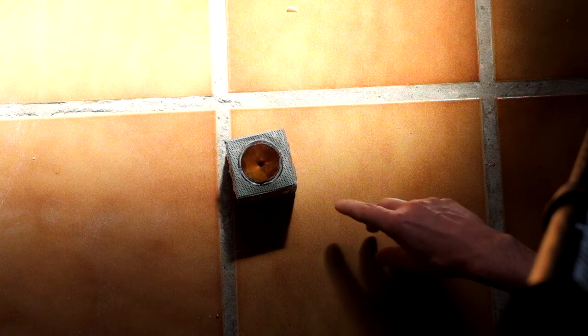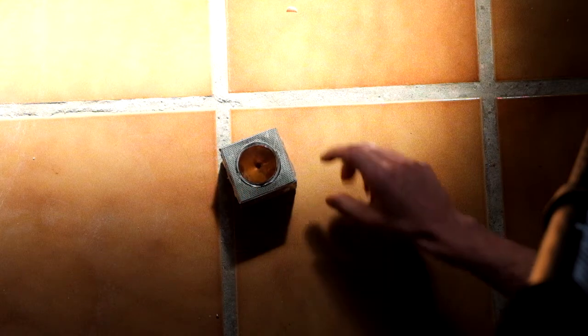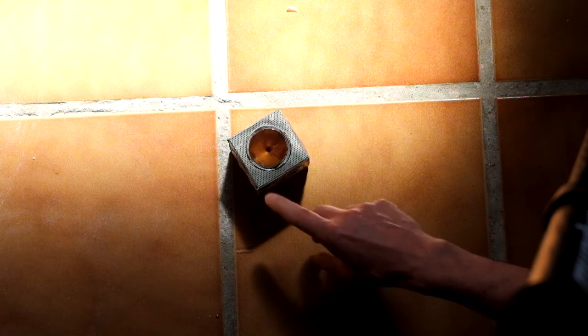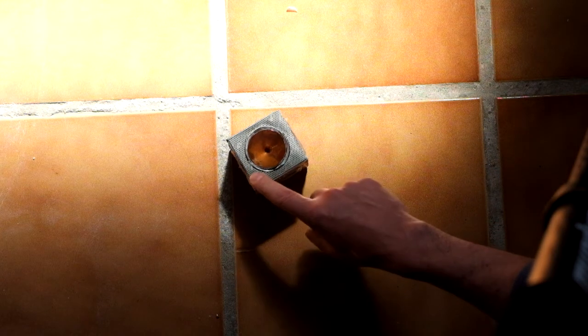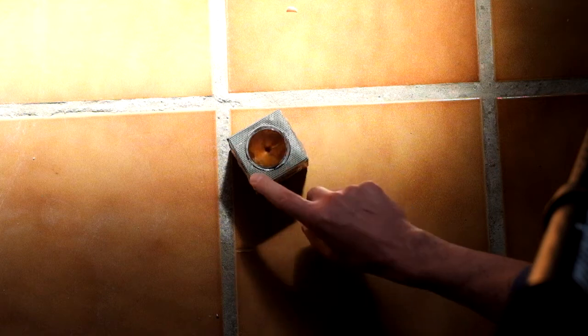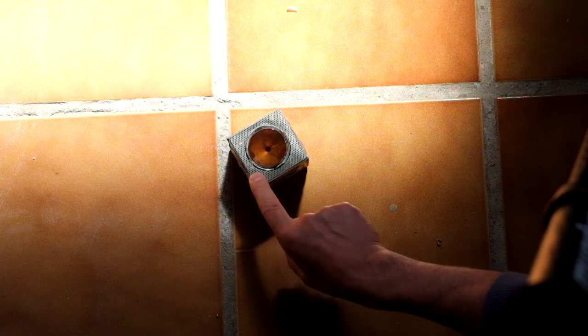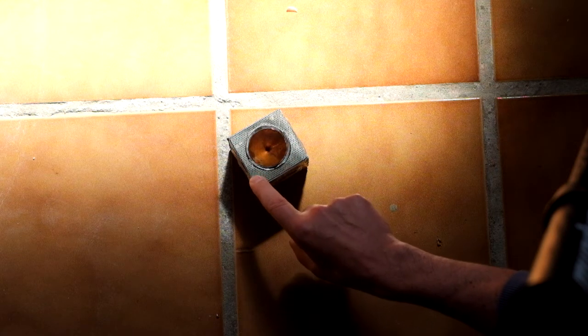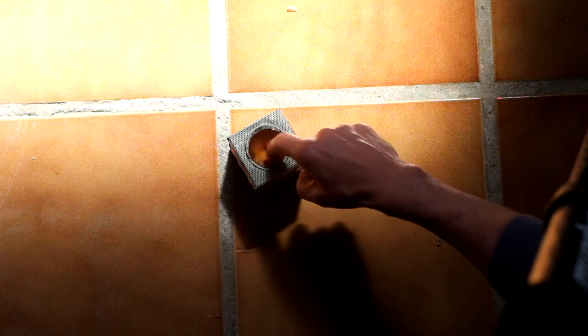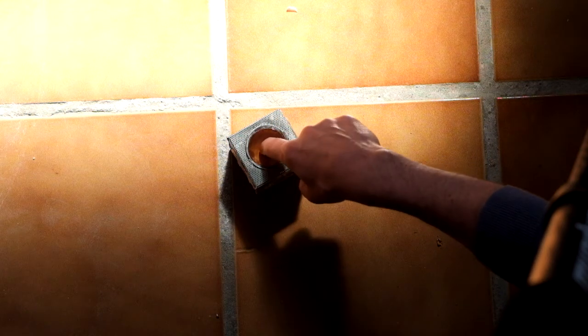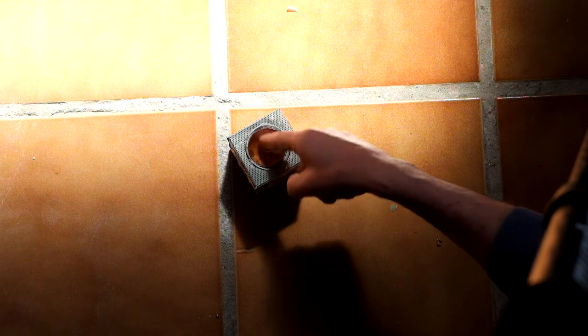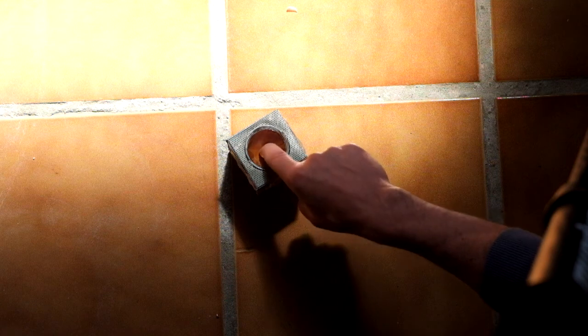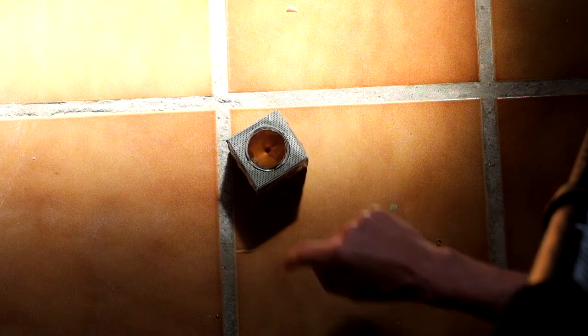When it is grounded, you have to ground the casing, and I ground that with my body. I touch the casing and measure the potential in between the casing and the inside, or the surface of the copper cone, because that copper cone is electrically isolated from the casing.